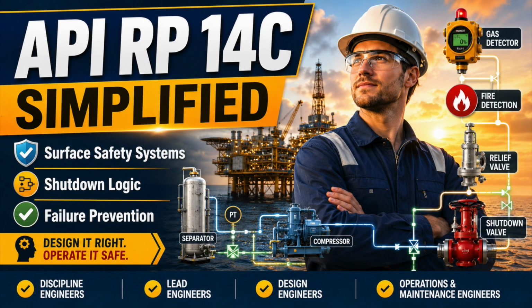Heat exchangers must be analyzed on both sides independently. The shell side and tube side can have different pressure ratings and different fluid hazards. A tube rupture can expose the low pressure side to the high pressure side. Relief capacity may therefore be governed by cross-flow through a failed tube, not by normal operating flow. Treat the dividing wall as a potential failed boundary.